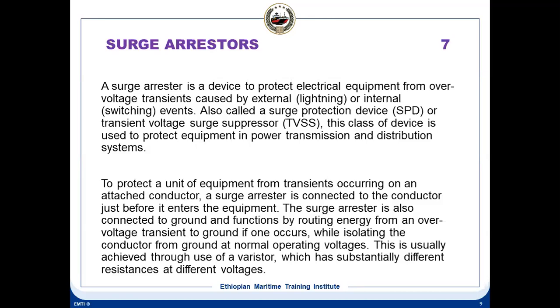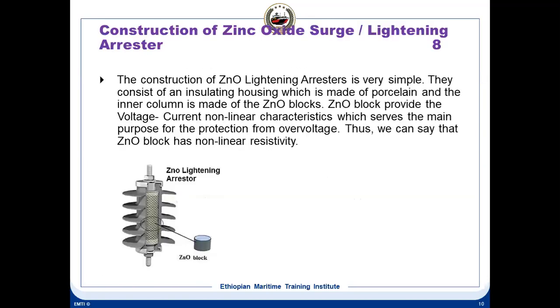To protect a unit of equipment from transients occurring on the attached conductor, transient meaning spikes, a surge arrestor is connected to the conductor just before it enters the equipment. The surge arrestor is also connected to the ground and functions by routing the energy from an over voltage transient to ground. So it can be connected between a phase and ground also, while isolating the conductor from the ground at normal operating voltage. This is usually achieved by using a varistor, which has a substantially different resistance at different voltages. So this type of surge arresters, we don't use on board ship. It is used only on shore.